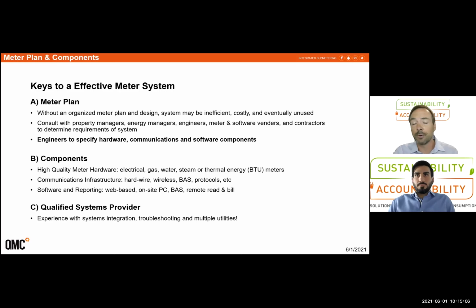You're going to have hardware installed that is not reporting, or you're going to have a nice software platform, nice meter hardware without a way of getting data from the hardware to the software, hence the communications requirements. And we do recommend that a qualified systems provider is involved, whether that's a commissioning agency, a meter manufacturer, or another group who can put the whole thing together and ensure that all three of those components are working well.